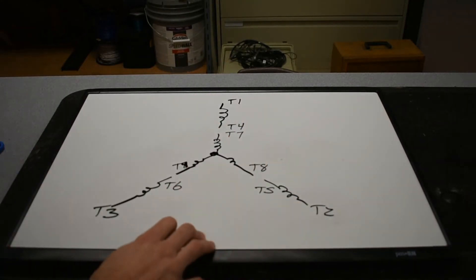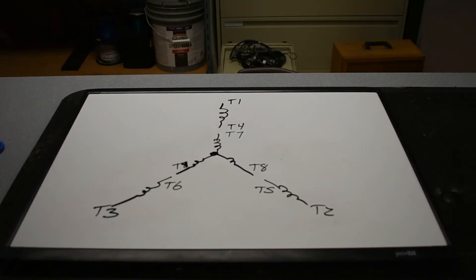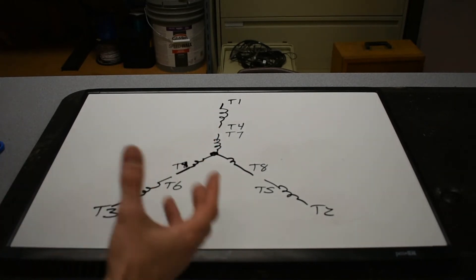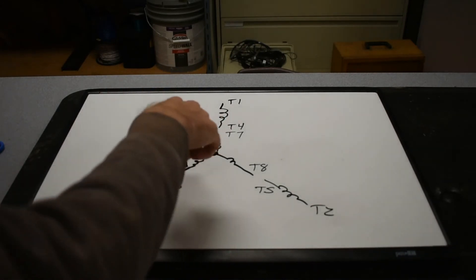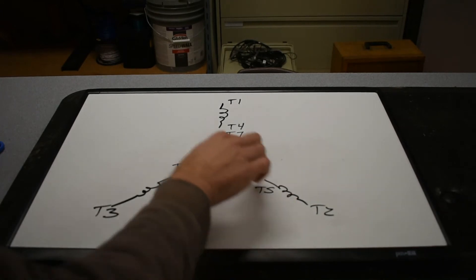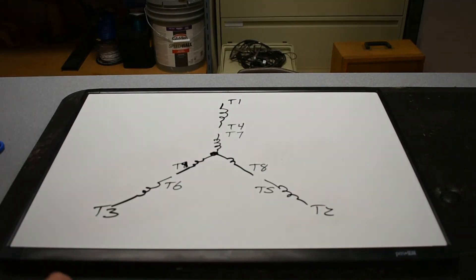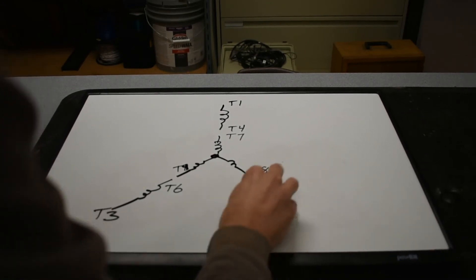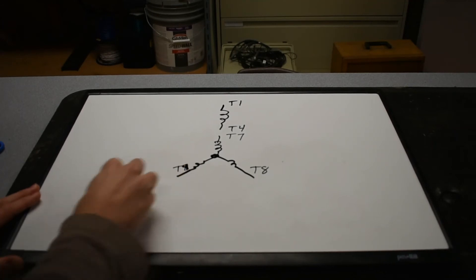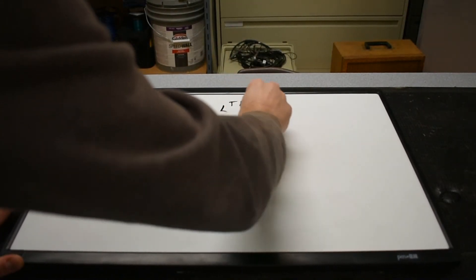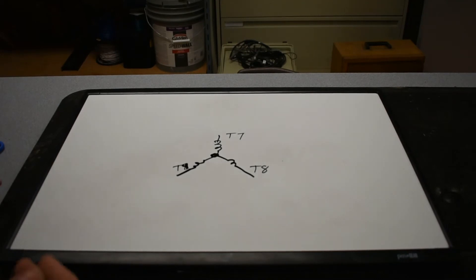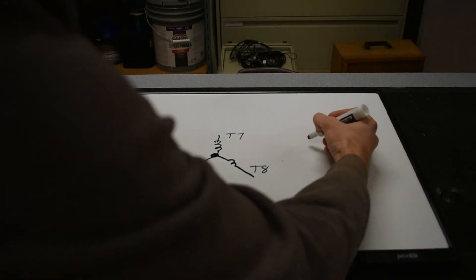So using it for lower voltage, lower voltage is not putting all the coils in series with each other, but rather we're going to take these three, the ones that we can access both sides, and we're going to take one end of each and tie them together so they actually form a second one of these little upside down Ys in here. Then we'll be able to tie the incoming line wires to both of those little upside down Ys. So I'm going to erase these three coils and basically redraw them by themselves over here next to this one. So it's like creating two of these little tiny things parallel with each other. In fact, that's the whole key here. The last one was connected with all those coils in series with each other. Series allows higher voltages to be dropped on single coils. But in parallel, which is the way we're going to design this, it allows those voltages to be dropped side by side with each other, which means a lower source voltage needs to be separated over fewer resistors.